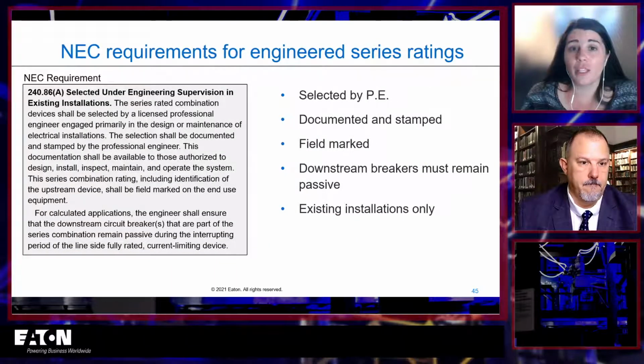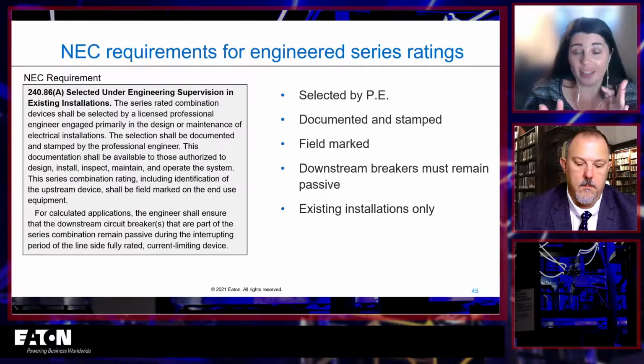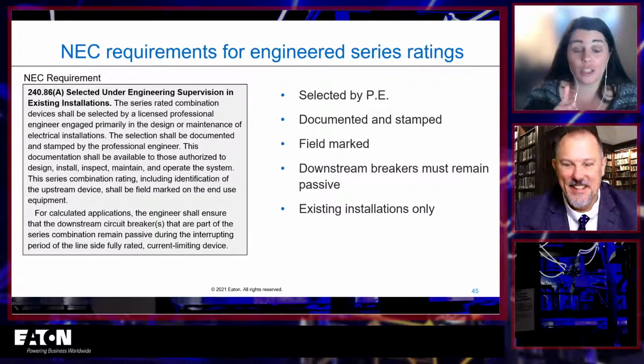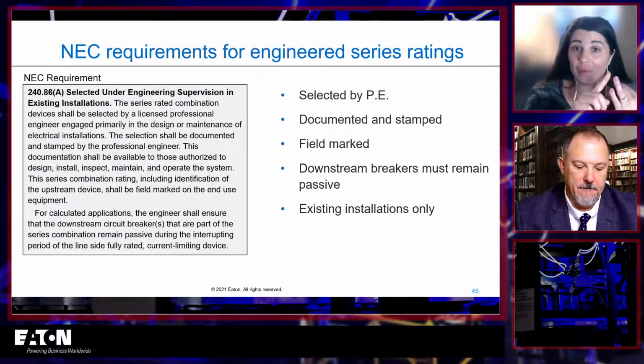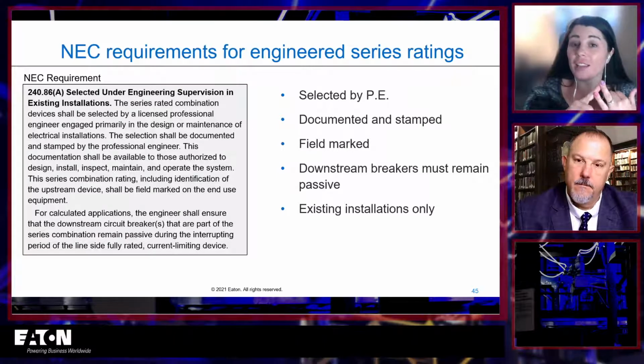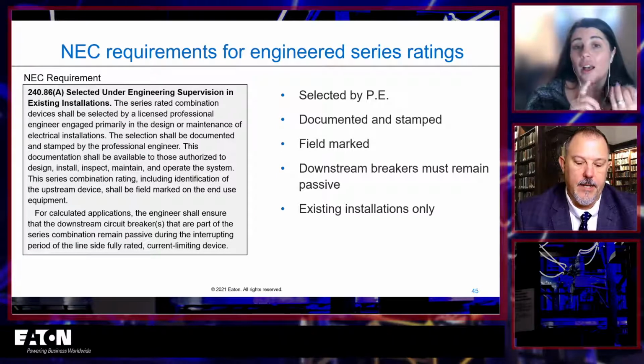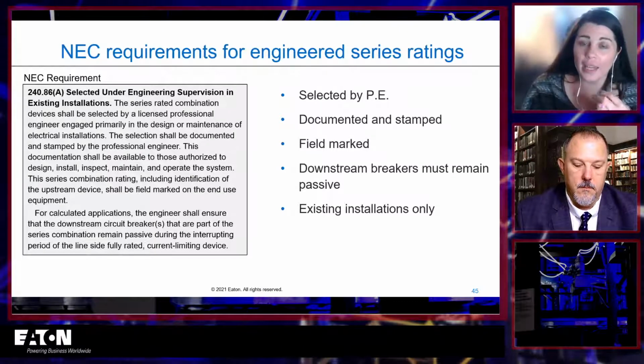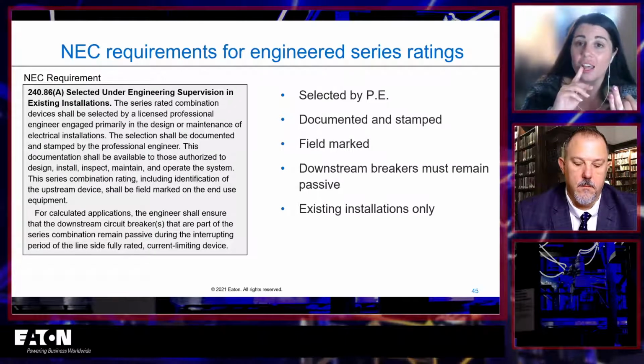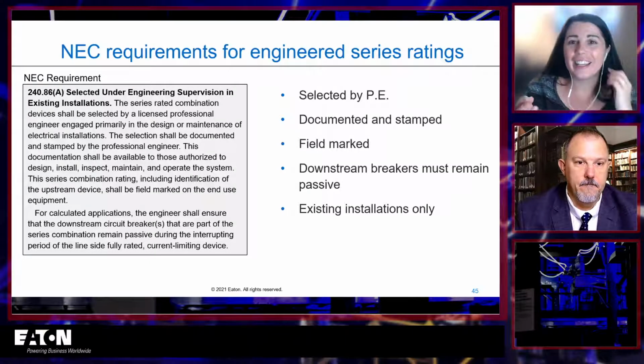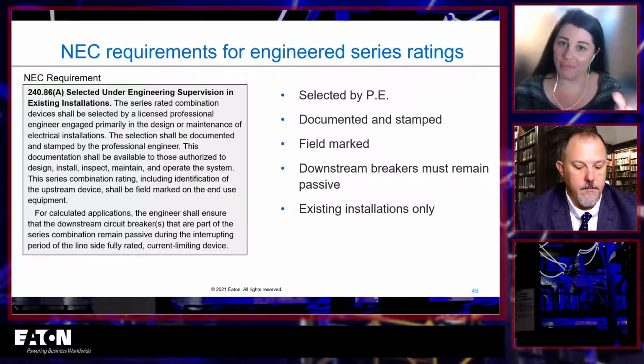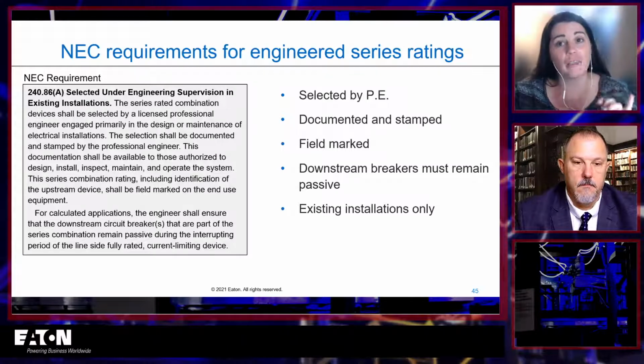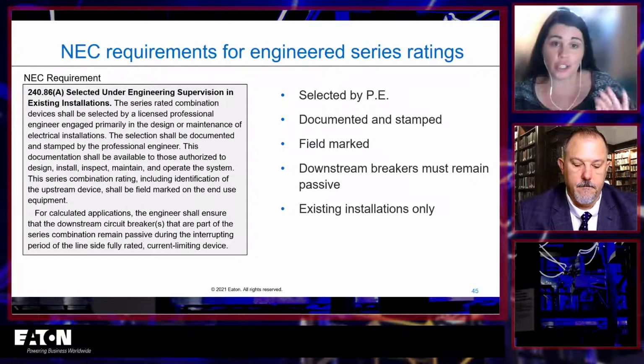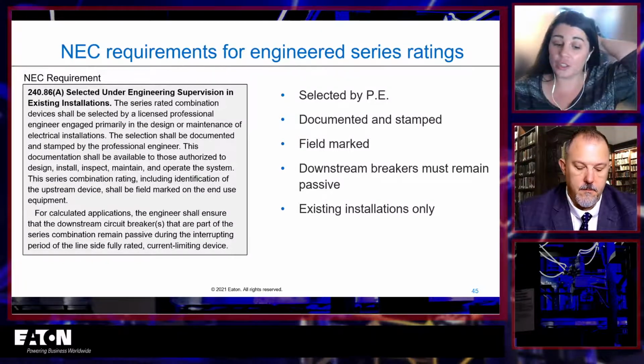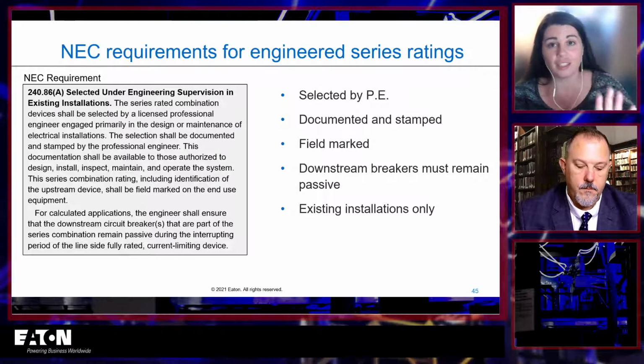You'll see the requirements for an engineer's series rating, and I basically recommend nobody do one of these. It has to be done by a PE, and they have to stamp it. So if you're a PE, you have to be really, really confident, because you're testifying that these are going to work together. There are so many tested series combinations that use one of those. Why would you go out on this limb? There's a lot of liability in using this engineered series rating. So just try to use a tested one.